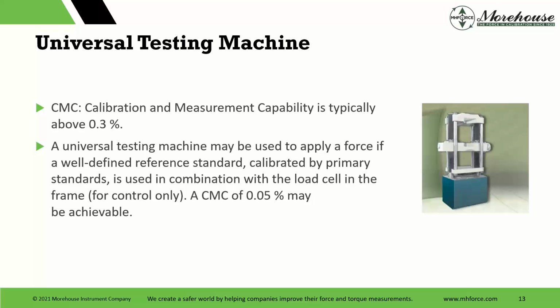And if it's used with a load cell, where I really wanted to make the point here is, you have this machine, it's controlled. In almost all cases, you need to buy an additional reference standard load cell, because the load cell that's in the machine is your control load cell, and then you buy a reference, have that calibrated by a reputable laboratory, and use that to make measurements. And then a CMC of 0.05% may be achievable, but there's a lot of hurdles that you have to go through to get there, and you have to do it right. I'm more than happy to help people get that right, because what it amounts to is, likely you have the machine, it amounts to adapters and either purchasing a load cell from us, and then we calibrate it with dead weight, or sending us a reference load cell to be calibrated in dead weight with primary standards.